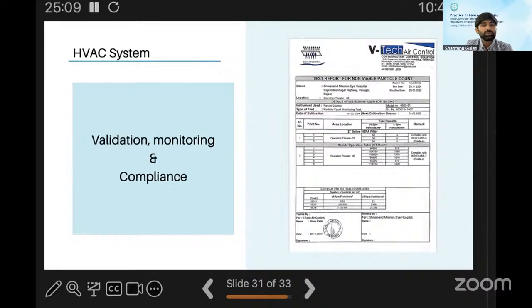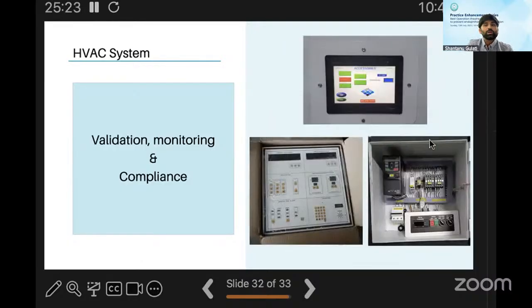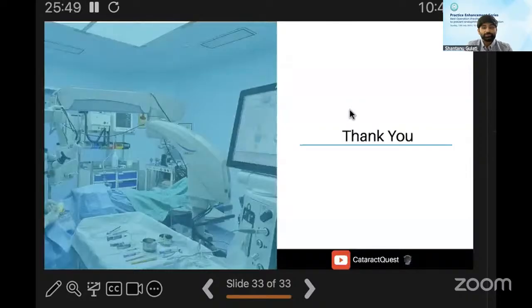At the moment you start your OT, and about every 6 months, we get our AHU validated. As can be seen here, at the level of the grill it is ISO class 5, which is a class above the requirement of ISO class 6. Also for validation and monitoring, there are surgeon panels. What you see here on the bottom right is the most basic one, and as you go above it, they become more expensive. On the left is the membrane panel, and on top is the Android unit. The only advantage with the Android unit is that it stores all the data, so you don't have to log the pressure, temperature or humidity manually. Thank you.